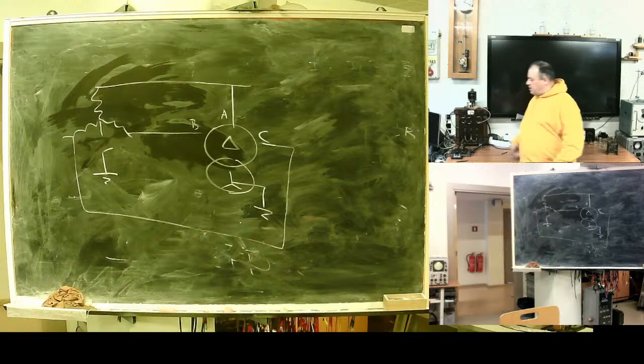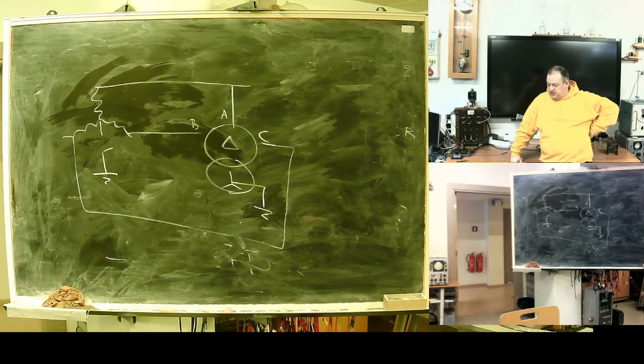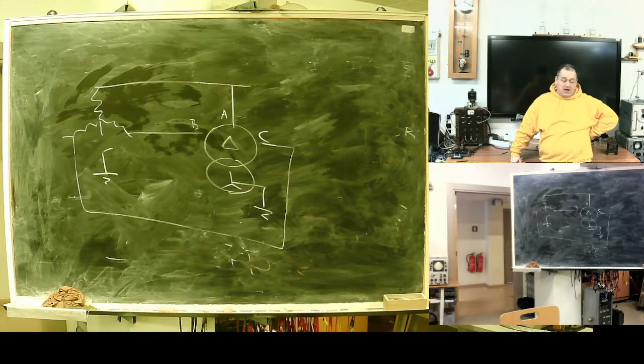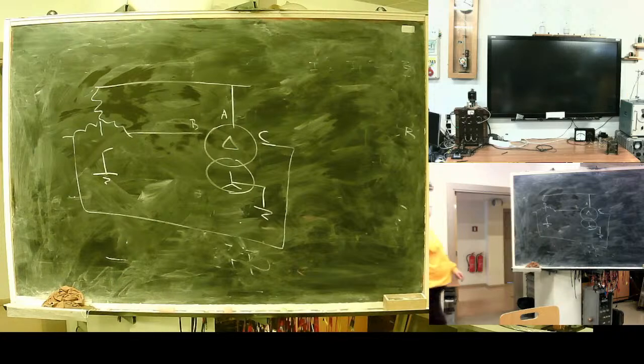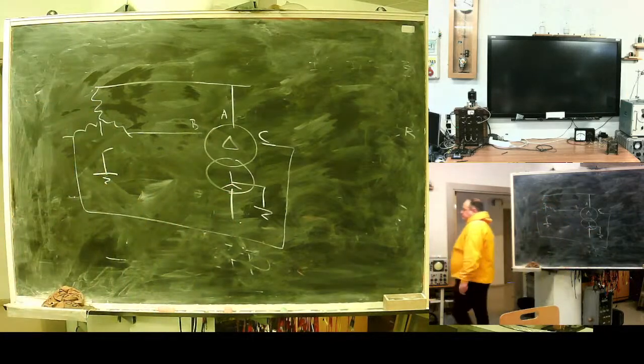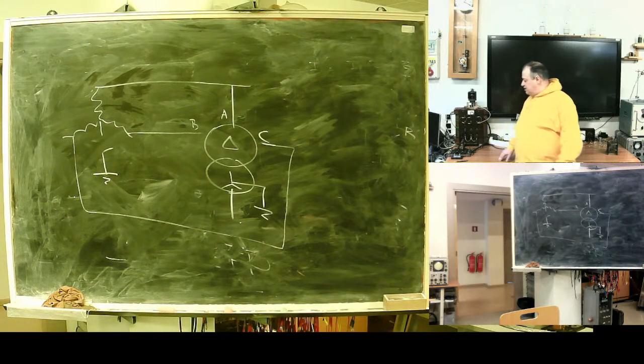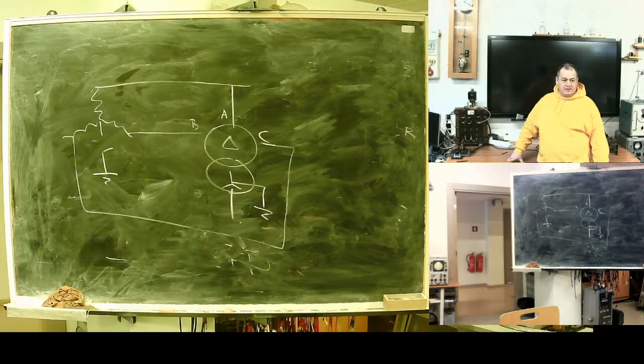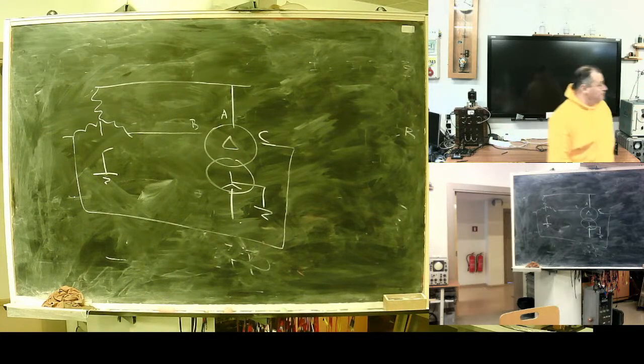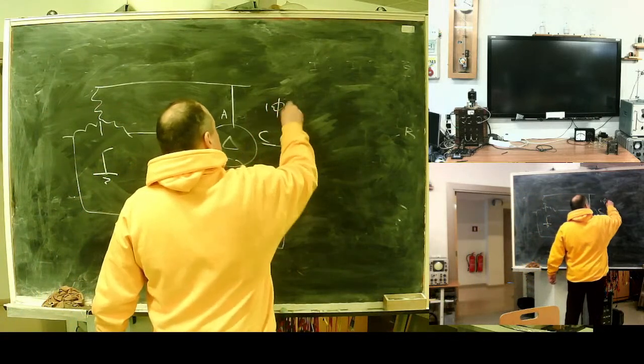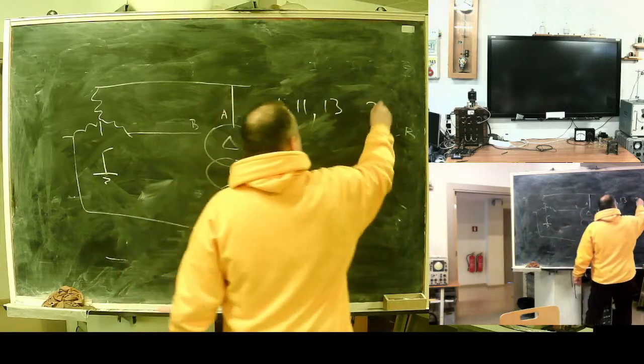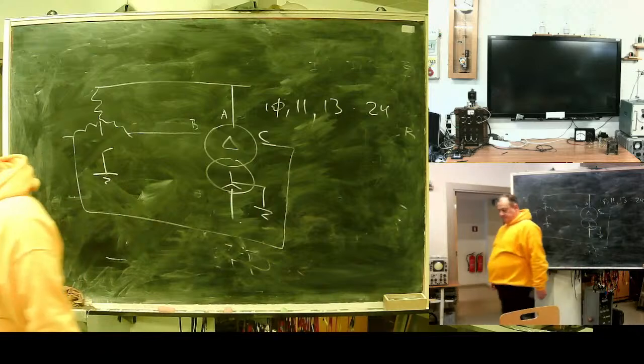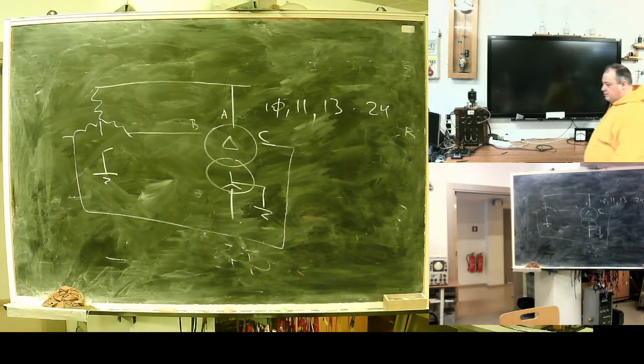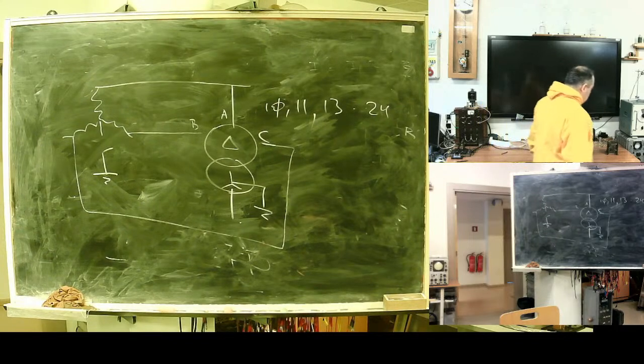What's connection of this transformer? Yes, it's a three-phase transformer. But what's the connection? Star. On which side? Here is primary side, here is secondary. What's the connection on primary side? Primary delta. Delta and secondary? Star. Here can be 10, 11, I don't know, 13, 24 kilovolts, something like this. There is no need for single phase.